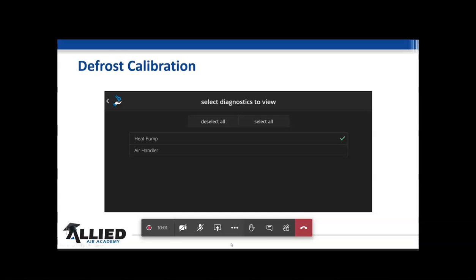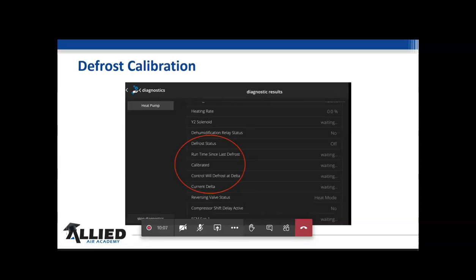So I'm going to check the heat pump, and down here at the bottom, it's going to have run start test. So when I hit start test, this comes up. Now, I just got an email a little while ago about some updates that have been pushed out. This may be a little bit rearranged, maybe a little bit different on your stat, but the control will defrost at delta, current delta, and run time since last defrost, that'll all still be there.